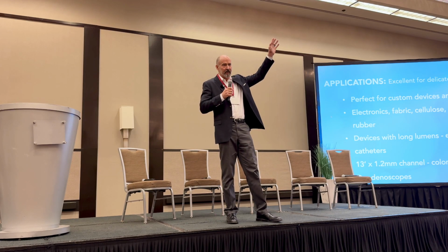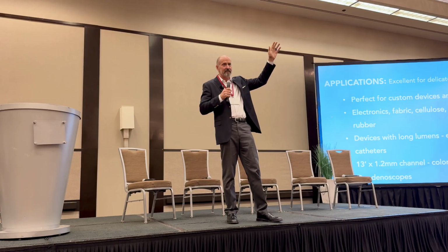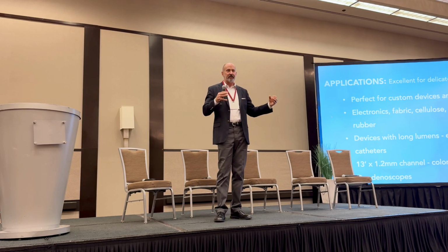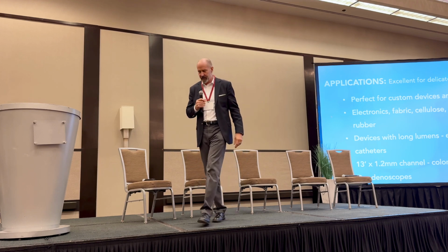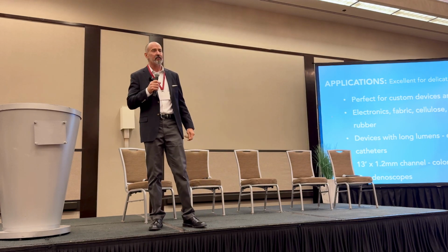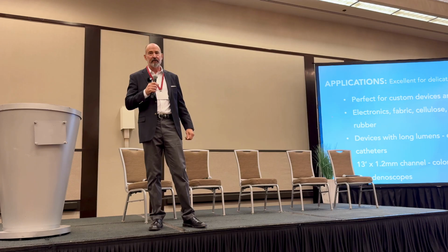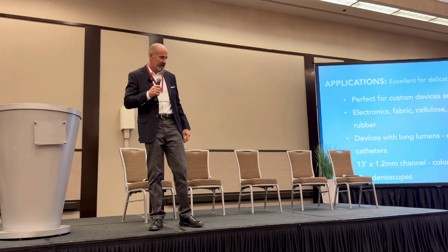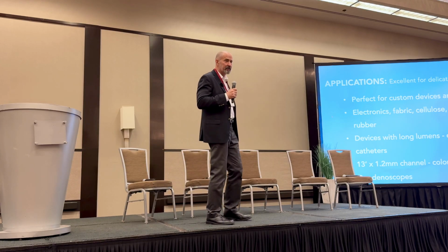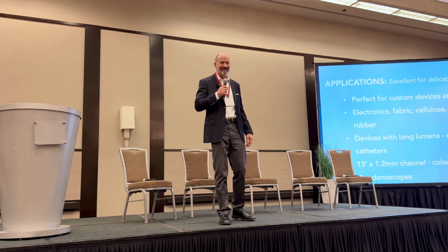Now, how many people here are familiar at all with the engineering of duodenoscopes? Okay, so it's basically an endoscope that has on the distal tip, on the end, an elevator mechanism that allows it to pivot 90 degrees. And that pivot point turns out to be exquisitely difficult to sterilize. And for 2 years, we came up with negotiated agreements with FDA on how to test these most difficult devices.